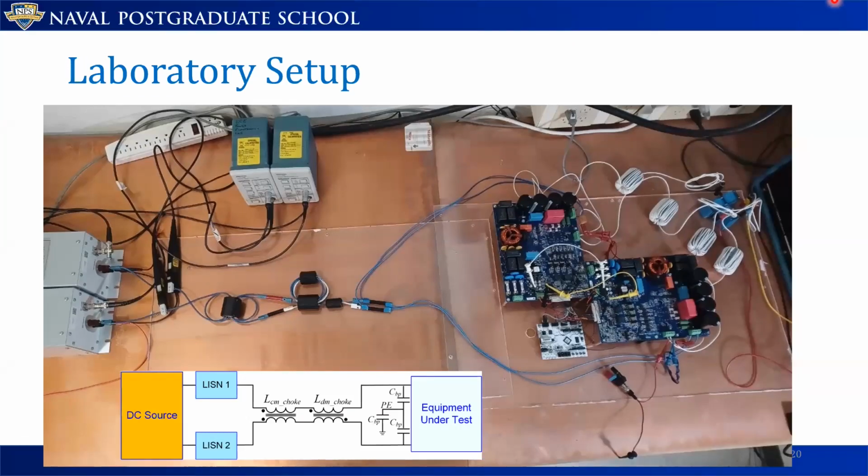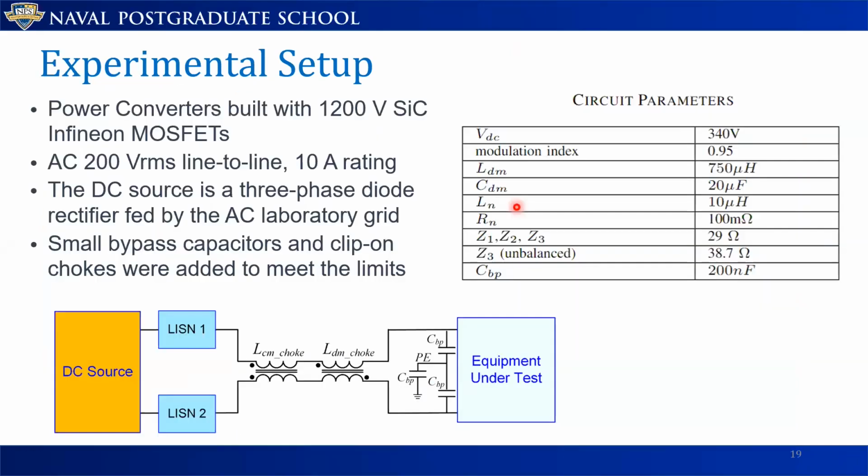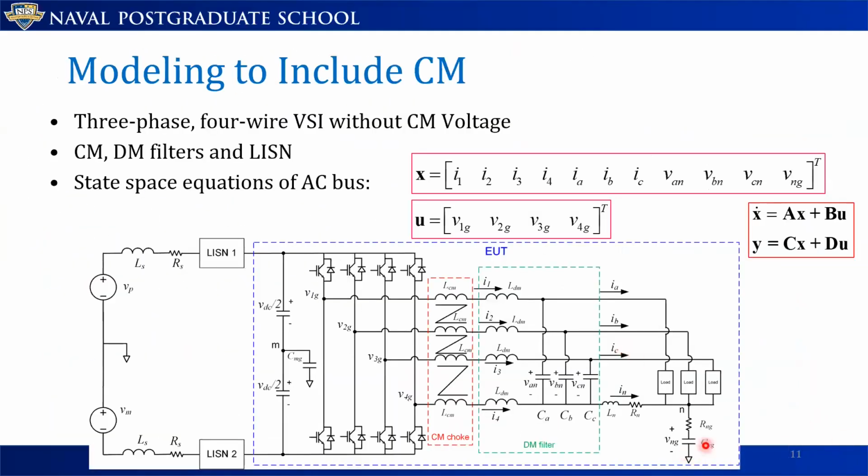Could you talk on how to estimate the common mode winding to ground motor capacitance experimentally or with FEM simulation tools? So the grounding capacitance between the load and ground, right? You're talking about this one, the CNG. Okay. There are papers on this topic. In the 90s, we did one. For example, we did an entire set of experimental measurements on a motor, and we measured really all the parasitic components. We measured basically the frequency response of the motor, and then we plotted it using lumped parameters. So that's one way.